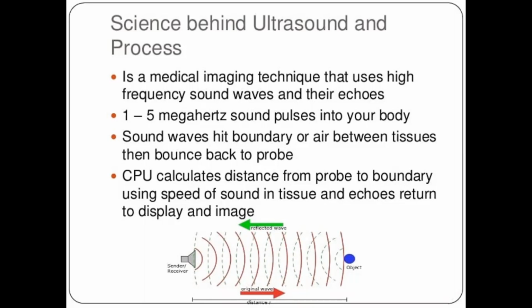Ultrasound has medical and non-medical uses. Even in industrial applications, they use ultrasound for other purposes. Those in the environmental field also use ultrasound to detect water sources. All these use even higher megahertz, but in medical ultrasound it usually stays around 2 to 2.5 megahertz. Sound waves hit boundaries or air between tissues and bounce back to the probe. The CPU, or central processing unit, the machine itself, which incorporates all the electrical components and software inside, calculates the distance from the probe to the boundary using the speed of sound in tissue, and the returning echoes are displayed as an image.